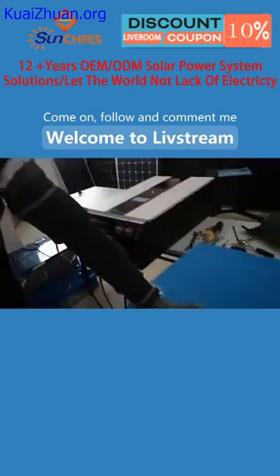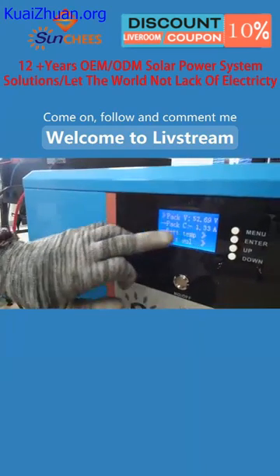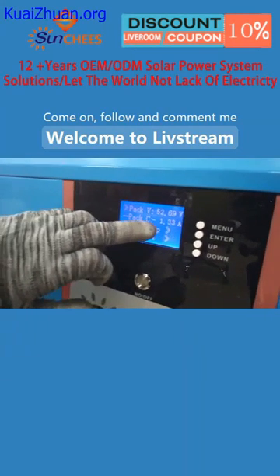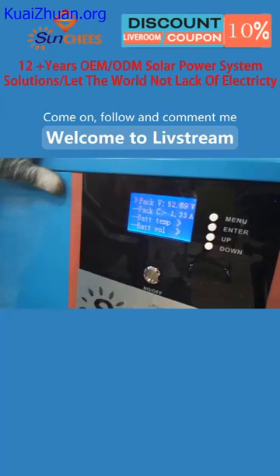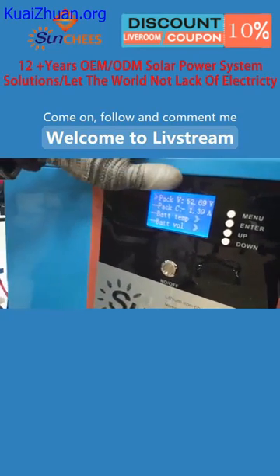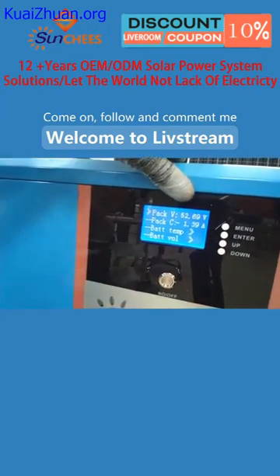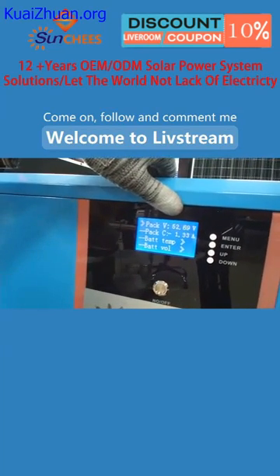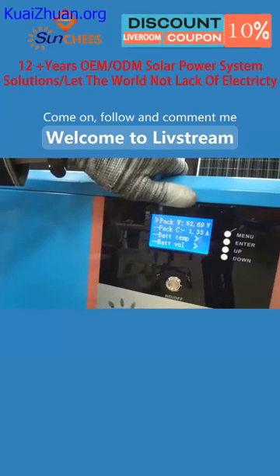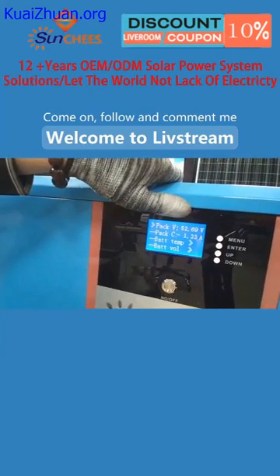You can also check the lithium battery screen. Right now, I did not turn on the loads, and the current on the battery bank is minus 1.33 ampere, right? About 1.33 ampere. This power is the self-consumption of the inverter. That means our 6 kilowatt hybrid inverter, the self power consumption will be around 65 watt. That is only about 1.5% self-consumption.